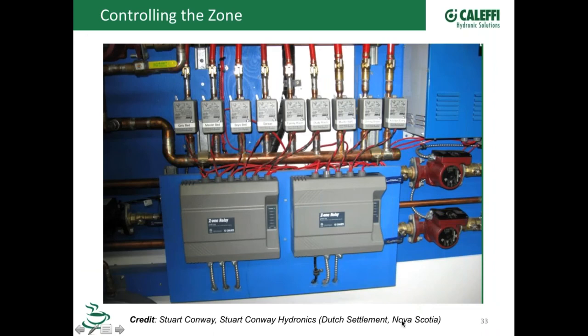just another nice picture from one of our contractors up in Nova Scotia. Thanks for sending that in. I like the way that he's wired this up here. You know, the high voltage wire going through the back of the board and going right to the zone valves. Nice about this is a lot of the zone valves come with 18-inch leads on them, and I think, in fact, those are our leads that come with it. So by putting the relays right at the valves like that, the leads that come on it will reach right down to the connections possibly.